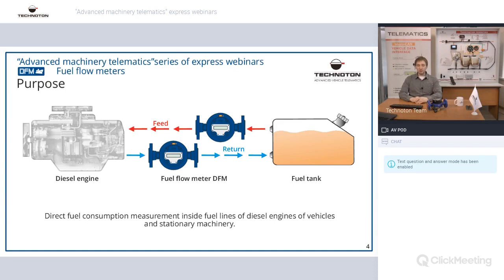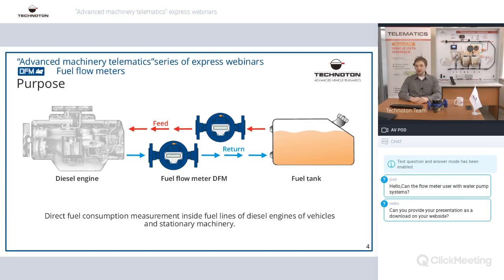The purpose of any flow meter is to measure flow rate — either instant fuel consumption in liters per hour, or total fuel consumption. On this scheme, you can see a flow meter installed on the supply or feed line, and one single chamber meter installed on the return line. That's a typical, simple fuel system for any vehicle, diesel generator, or machinery that consumes fuel. The only difference would be some burners that have gravity flow, with no pump delivering fuel from the tank to the engine.